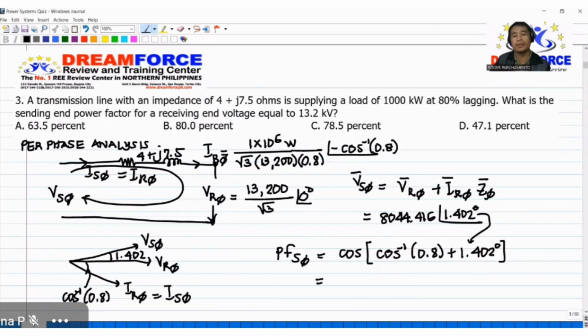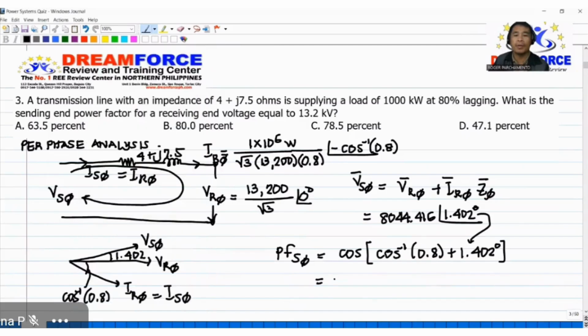So you take the cosine, maybe slightly less than the original power factor or the power factor at the sending end. So if it is not 78.5, it will be 63.5. Let's compute. Cosine of the arc cosine of 0.8, then plus the computed angle of the sending end voltage. So that is times 100%. 78.508. That will be letter C.